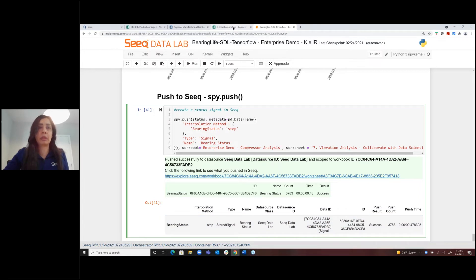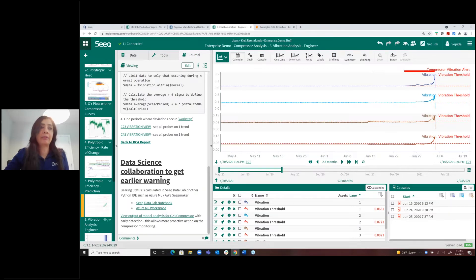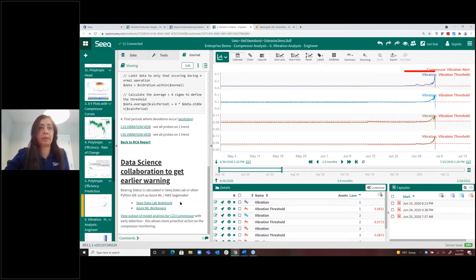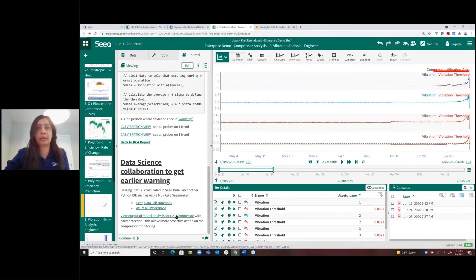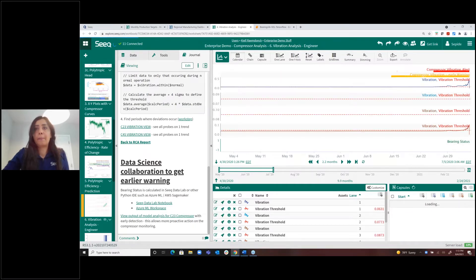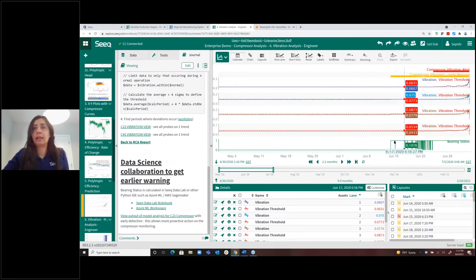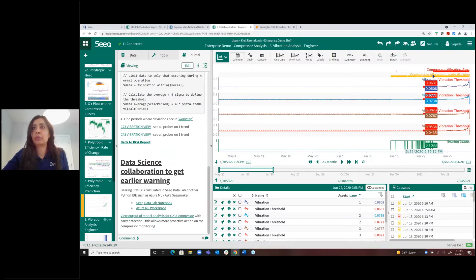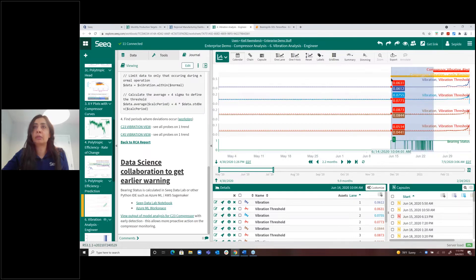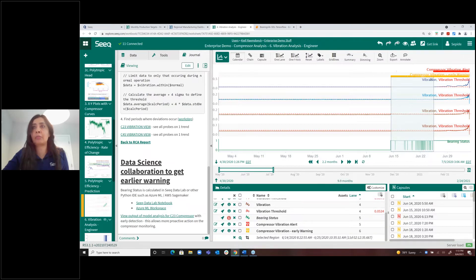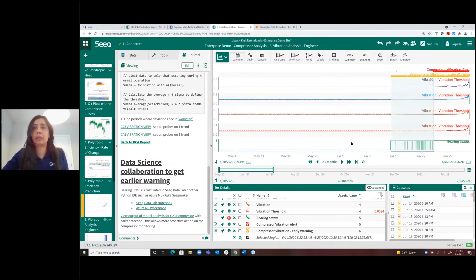Switching back to Workbench, now that we have the data scientist's model results, we bring them back and leverage the journal capabilities again. Using the bearing status signal and a value search to identify whenever the bearing status is 1, we created a second capsule condition. Using the machine learning model, we were able to get notifications 11 days earlier than the statistical analysis alone — helping us plan ahead for maintenance work.